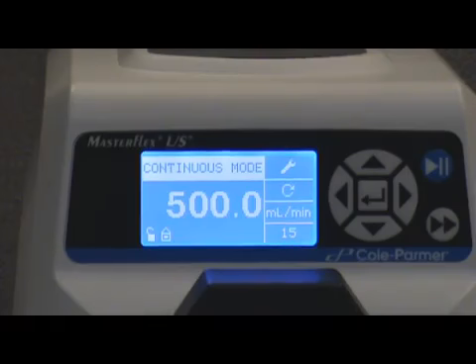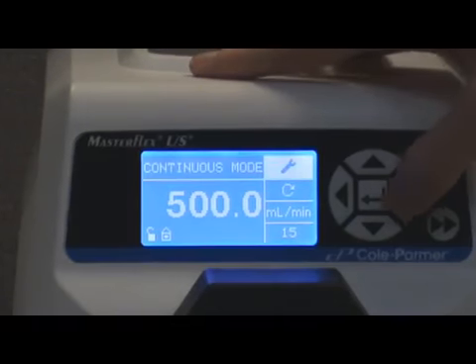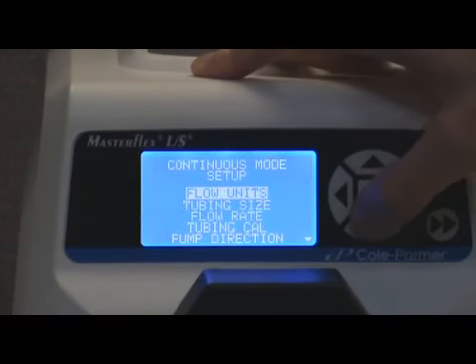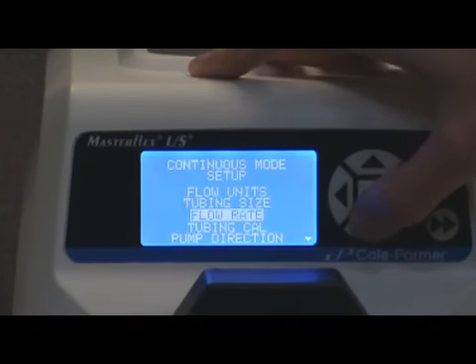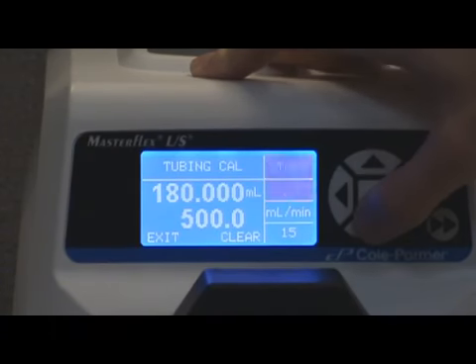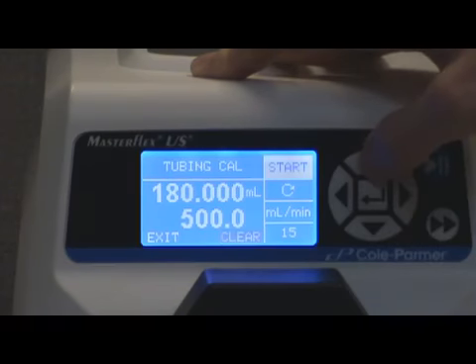Go to the main menu by selecting the setup icon and pressing the enter key. Use the up and down arrow keys until tubing cal is highlighted, then press the enter key. Set the drive for the desired flow direction, tube size, and flow rate. It is best to calibrate your tubing at the flow rate that you will be using in your application. This will ensure optimum accuracy when pumping.